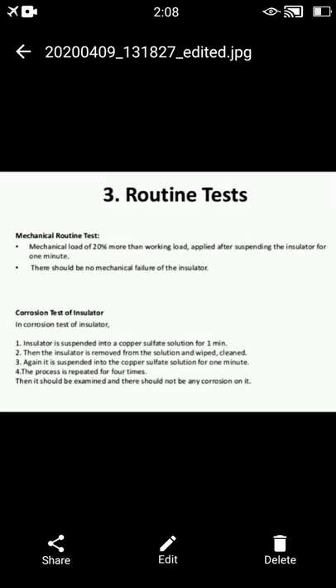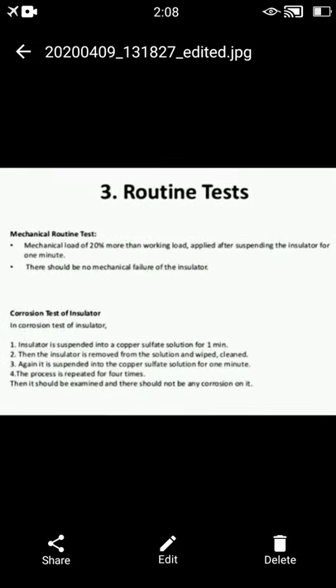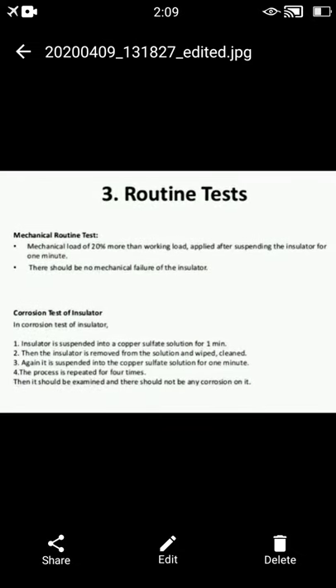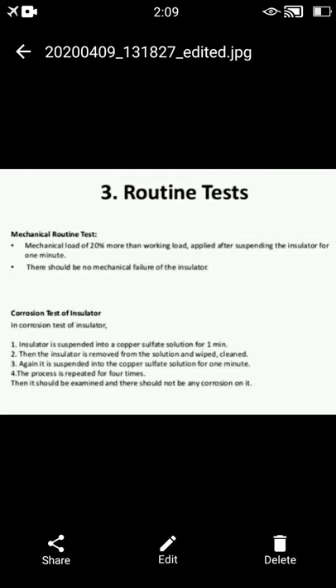The next type is called the routine test. As the name suggests, these tests are carried out routinely and are classified into two types. The first is the mechanical routine test, in which a mechanical load of 20% more than the working load is applied after suspending the insulator for one minute. After completion of this test, there should be no mechanical failure of the insulator.